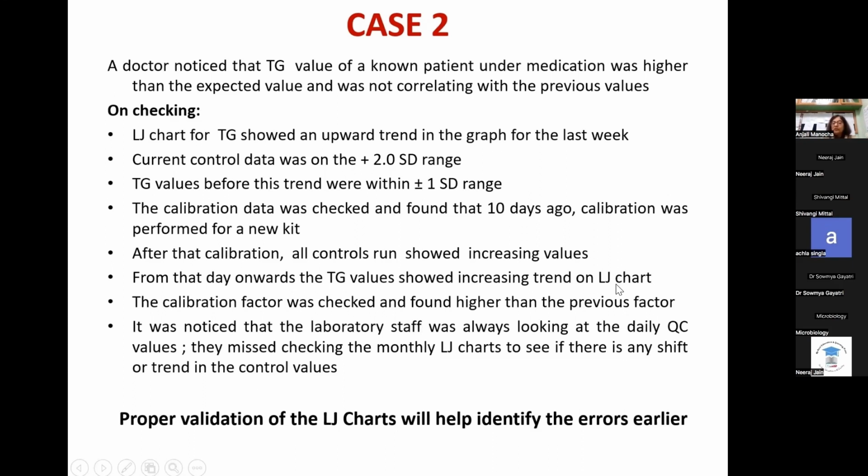So he said, okay, 10 days ago until today, there has been an increase in the value. There's a trend. So show me what the calibration was. How was the calibration done? What was the calibration factor? And they found that the calibration factor done 10 days ago was much higher than the previous calibration factors. And that is why the results were coming on the higher side.